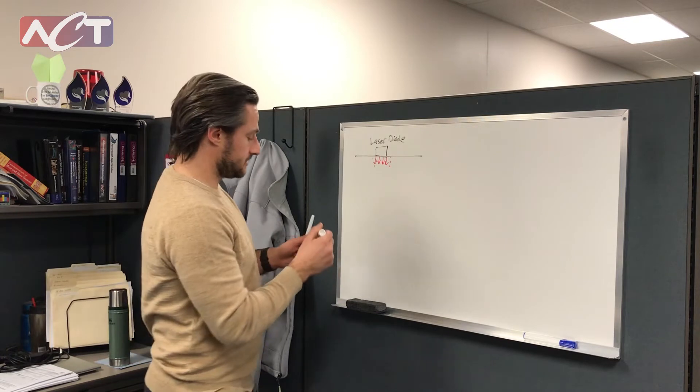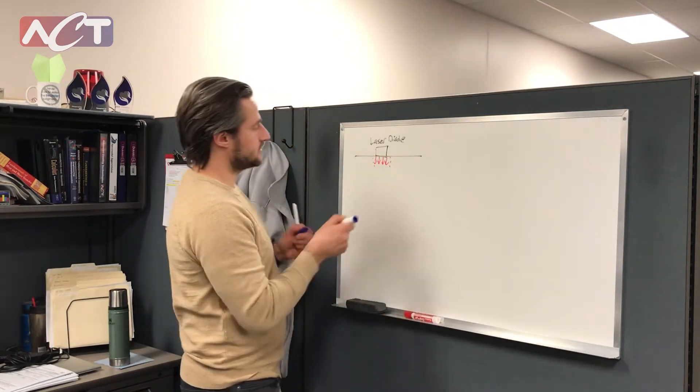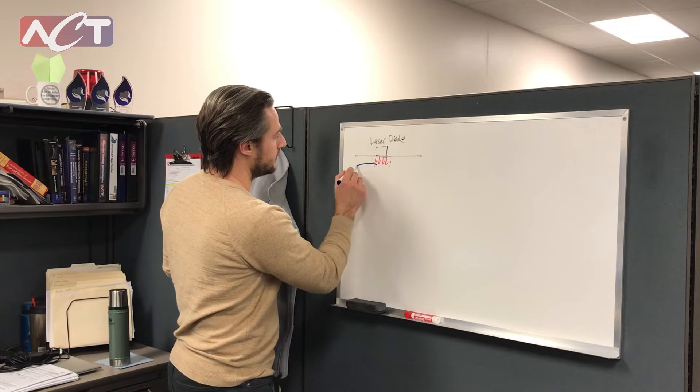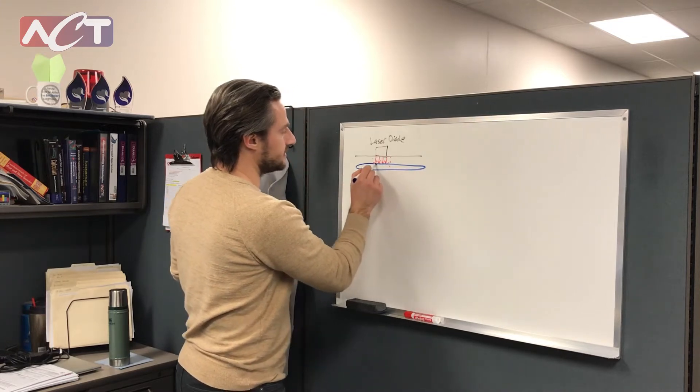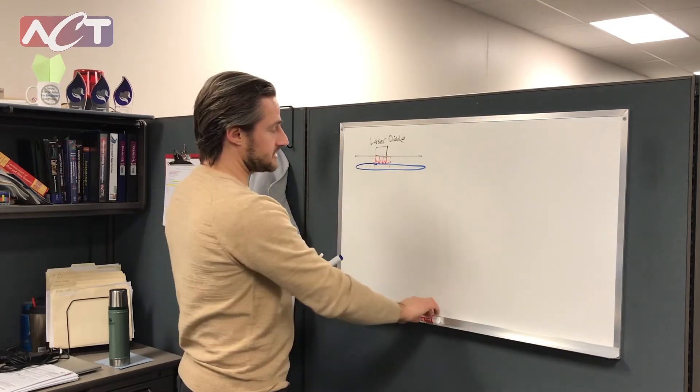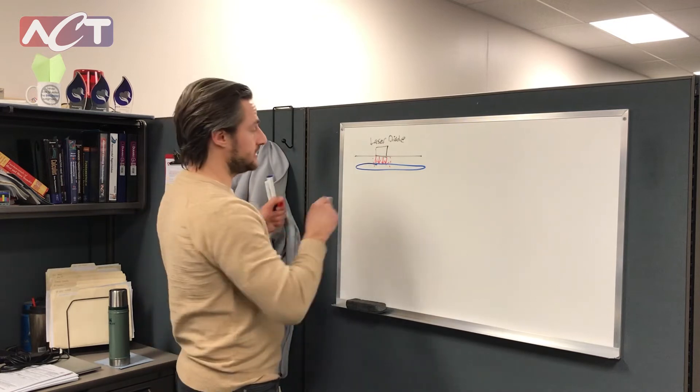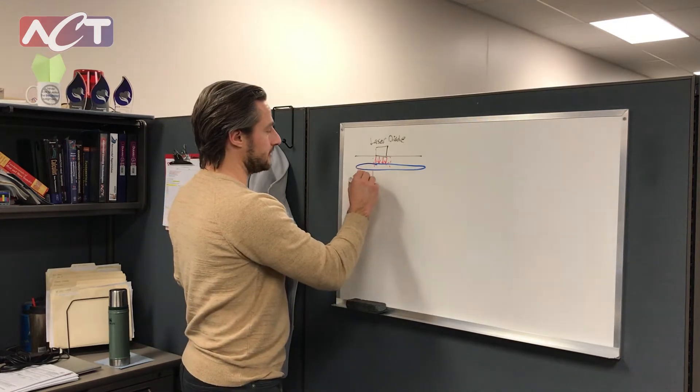One way to deal with this problem is to utilize a product like a heat pipe. So we take this concentrated heat load and embed a heat pipe inside of a base plate so that by the time our cooling solution sees this heat it's distributed over a much wider area.